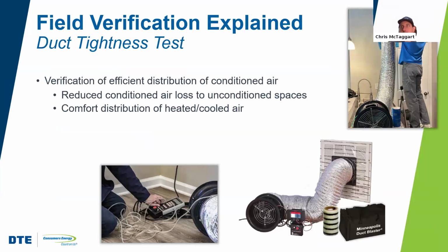Duct leakage testing is another main thing we do as an industry. Ducts can be tested for two different values. Duct leakage to outside tests how much heated and cooled air may be going into unconditioned spaces where ducts may live, like attics, crawl spaces, unconditioned basements, or garages. Then there's total duct leakage, which quantifies how tight the ducts are overall, whether inside conditioned space or outside.